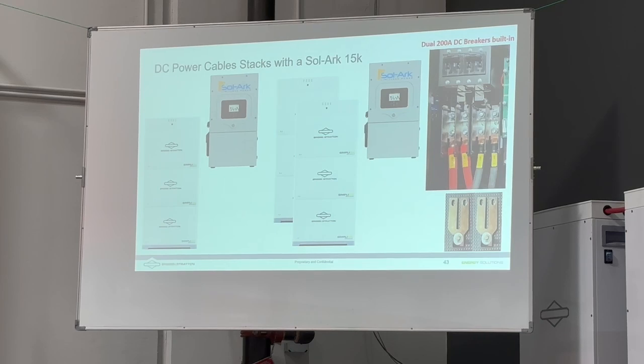So what do we do if we want to install multiple stacks with a Sol-Ark 15K? Well, one of the nice things about a Sol-Ark 15K is it's got the dual inputs. So there are two ways to do it with a single battery stack. You can either come out of the single battery stack with a 4-aught cable and come directly into these combiner bars that Briggs makes. Sol-Ark doesn't really want us to do that.